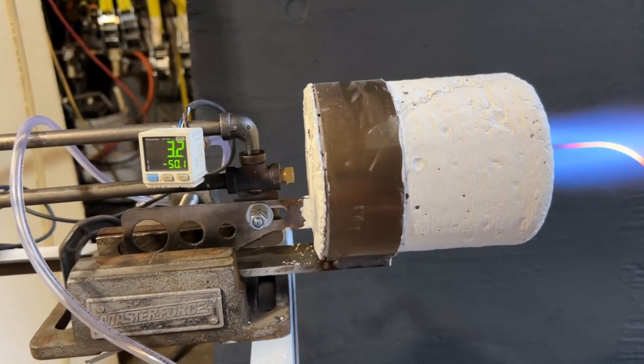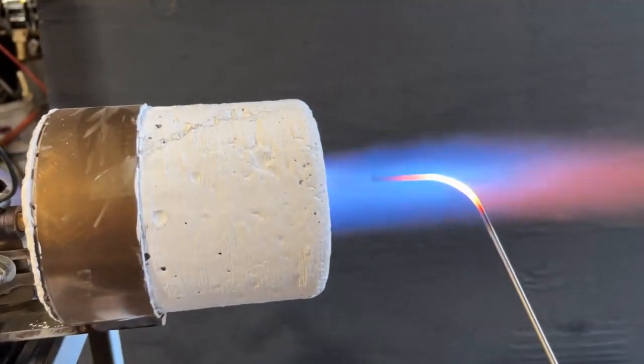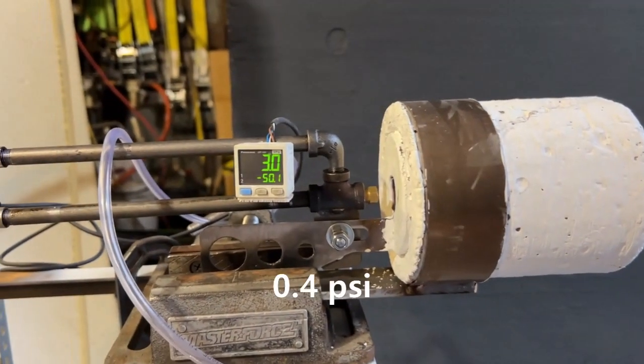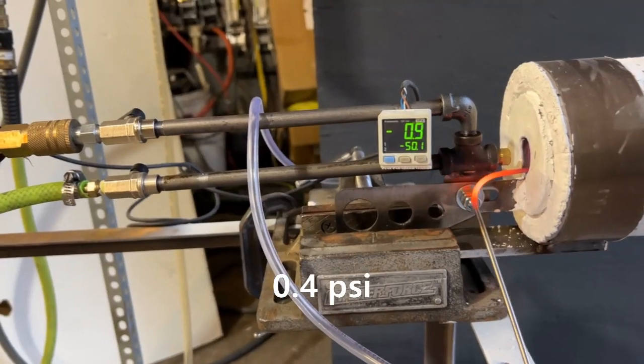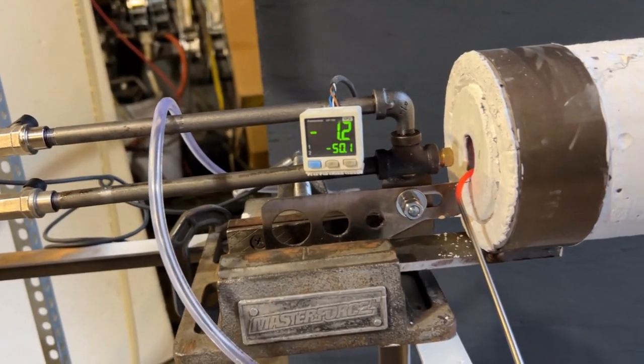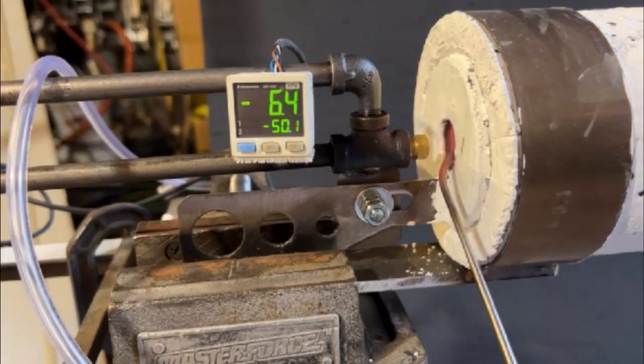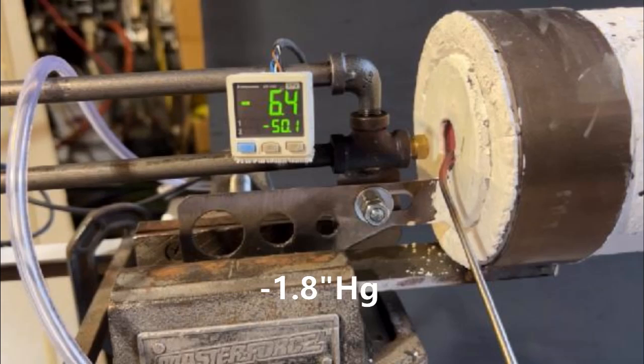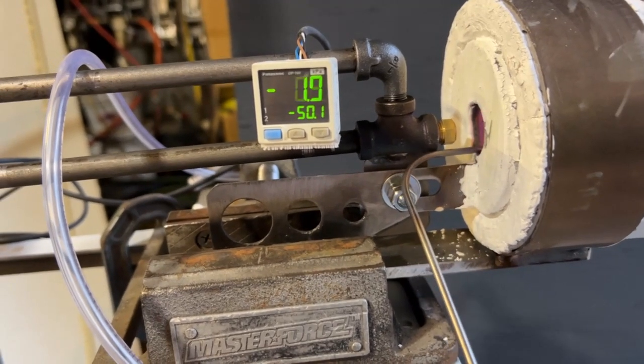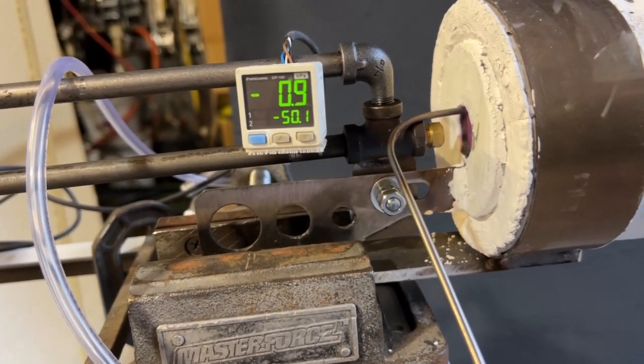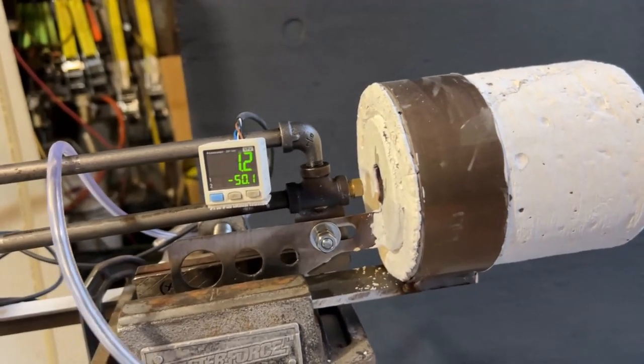So yeah it's going to be loud. Outside of the flame there we're at about almost a half PSI, so the fact that we're blowing about a half pound of pressure out of a one inch nozzle is pretty substantial. Right there's a vacuum of 1.8 inches of mercury which is a pretty good vacuum. You see there's vacuum all through the back end of this burner.